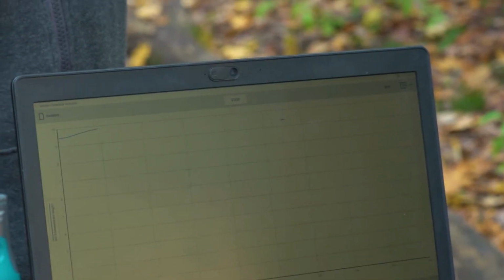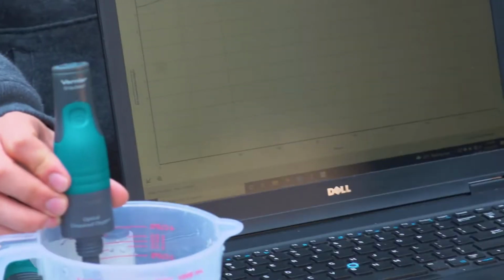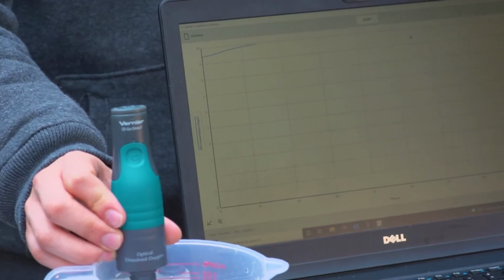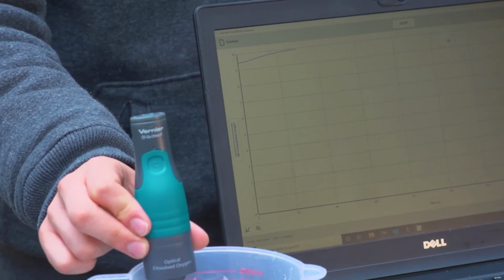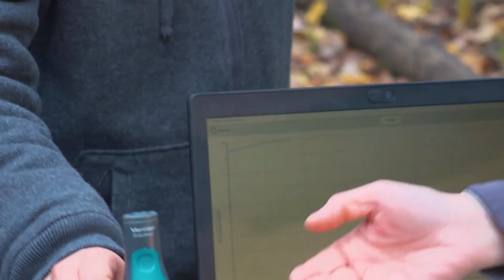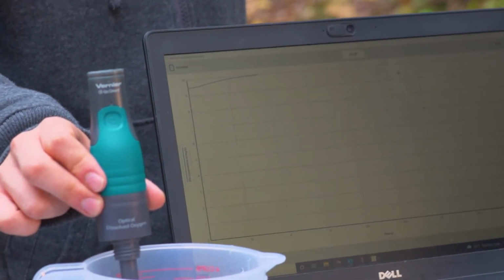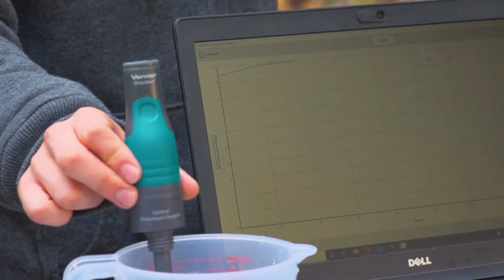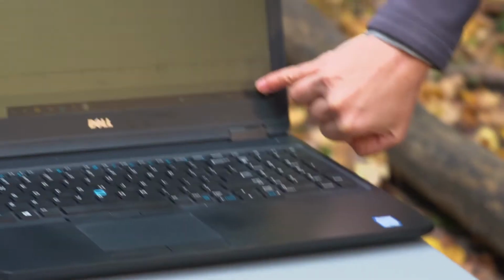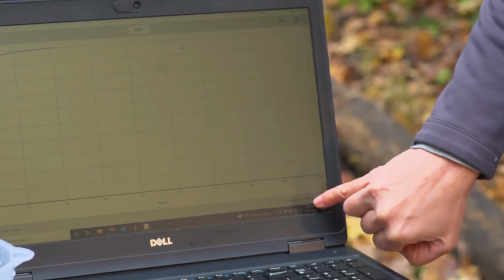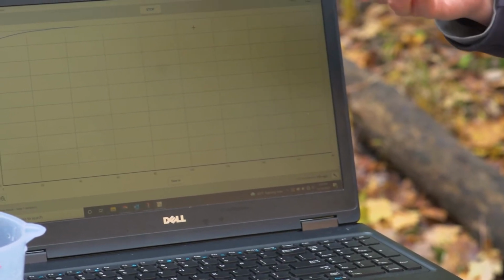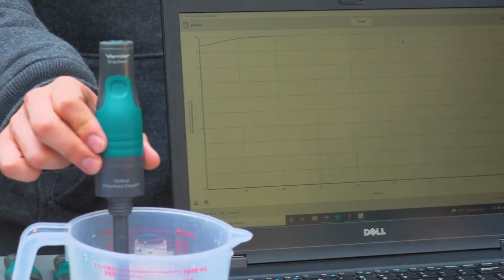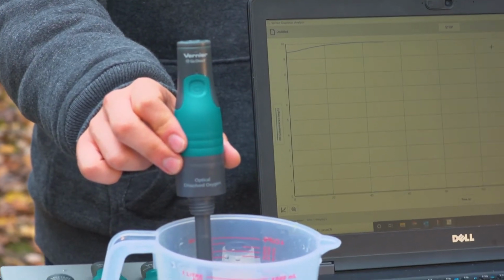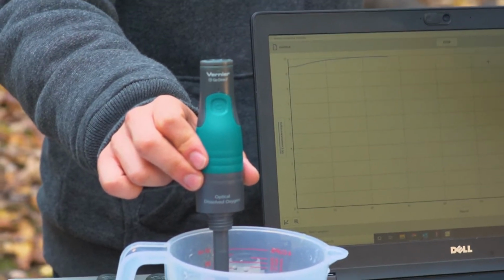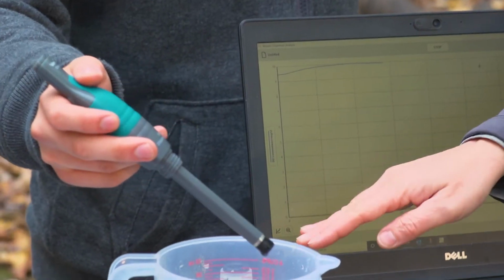And so you're just gonna wanna give it 30 seconds, a minute or so to get to a spot where the number is no longer changing. So you can watch it on the graph, and you can also see in the bottom right corner, it's giving us a numerical reading. So Jack, you're going to want to hold that just a little bit off the bottom. Excellent. And we can see this is stabilizing. It's getting pretty stable right around the 10 milligrams per liter of oxygen level, which is great news because when we did our chemical dissolved oxygen test, it was also 10 milligrams per liter. So we did a good job. Very good. So you can go ahead and take that one out.